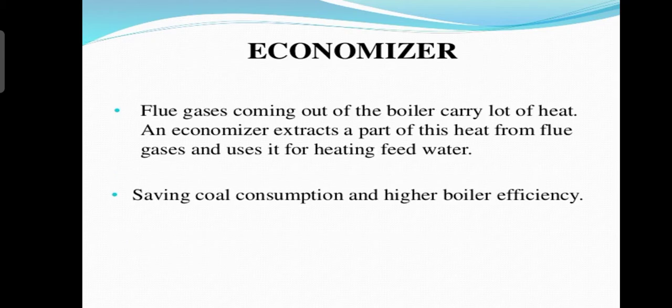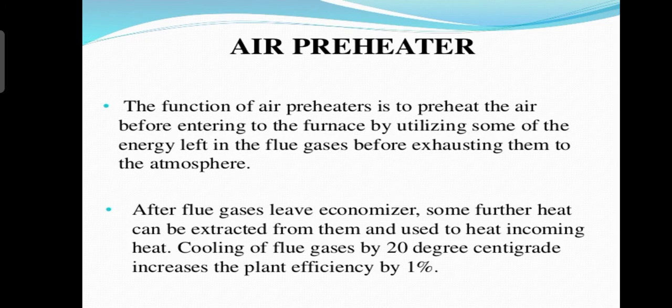Economizer. Flue gases coming out of the boiler carry a lot of heat, and the economizer extracts a part of this heat from the flue gases and uses it for heating feed water, saving coal and giving higher boiler efficiency.